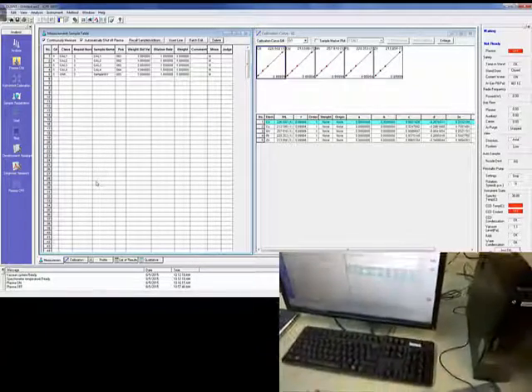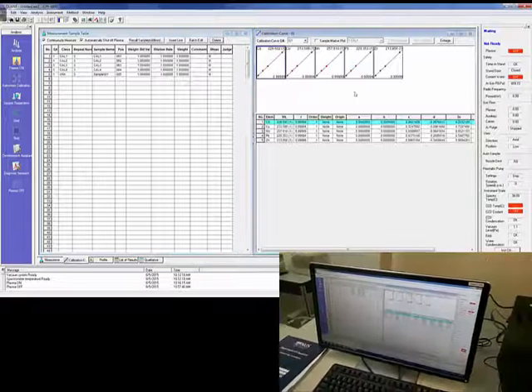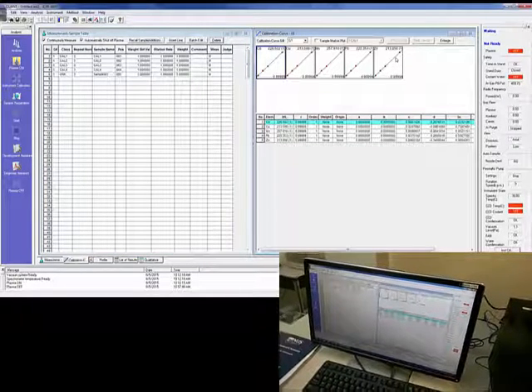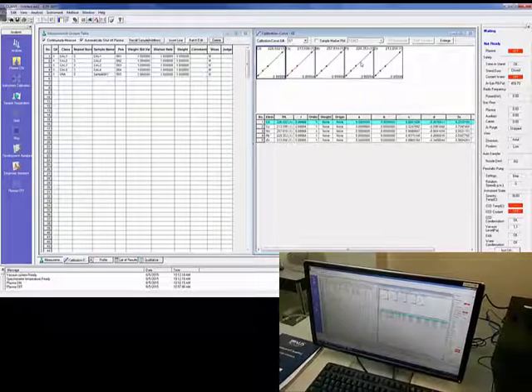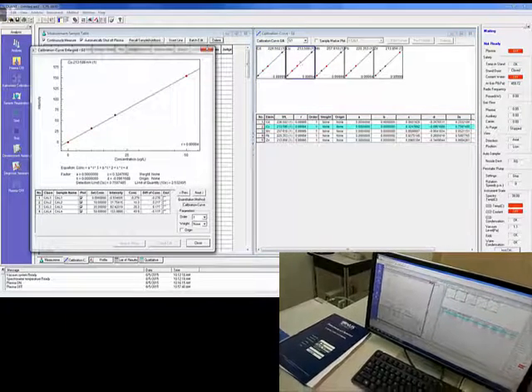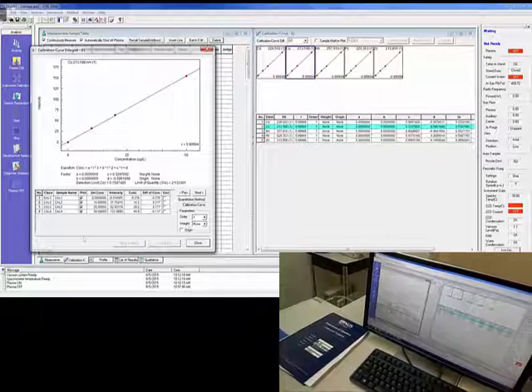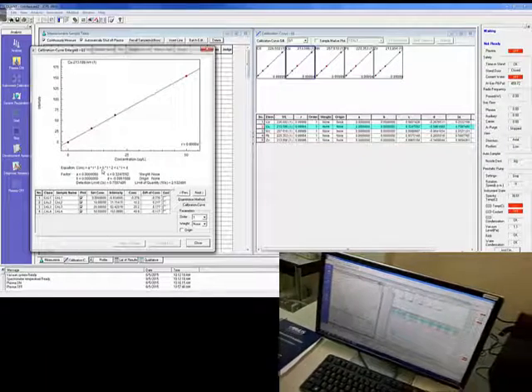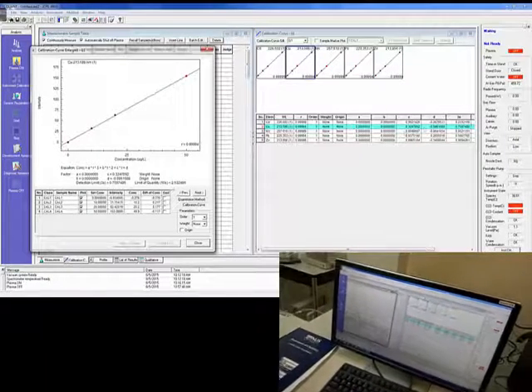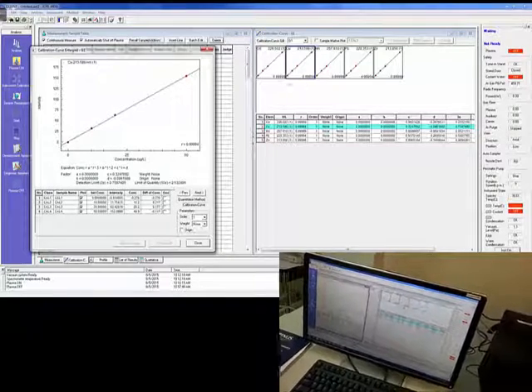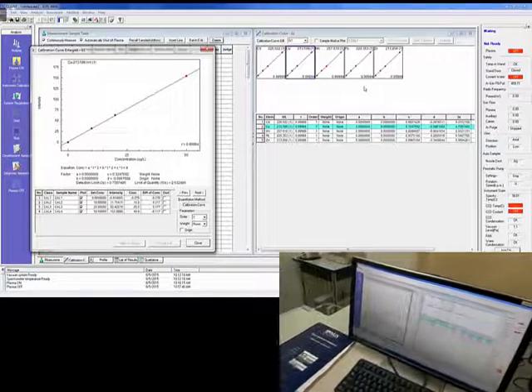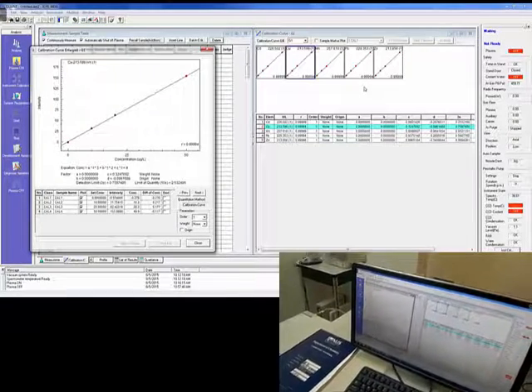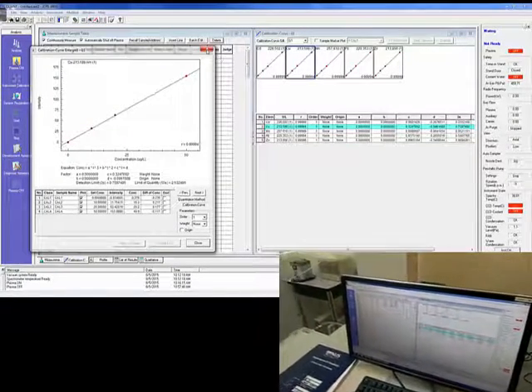So your screen will look something like this. Up here are your calibration curves for each element. And if we just double-click, you can see here that you then have the equation of the line with the various coefficients here. Note the r-squared values. Lots of nines in there. Always good news. And it means there are very few deviations from the line.